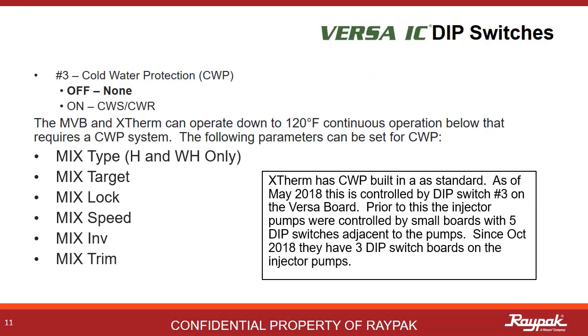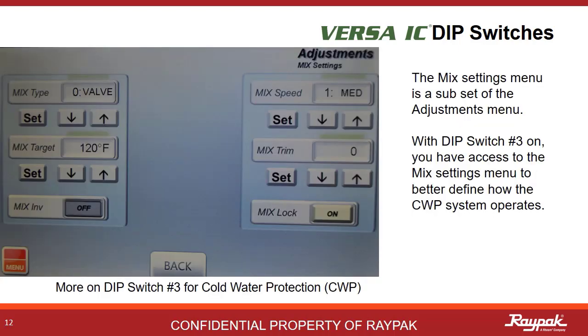Dipswitch number three turns on the cold water protection options. This family of boilers requires a minimum inlet temperature of 120 degrees Fahrenheit. The Xtherm has cold water protection as a standard feature. These menu items become available with Versa Dipswitch number three activated. With Dipswitch number three on, this menu will be available in the adjustment section. This is where you make changes to the cold water protection settings.